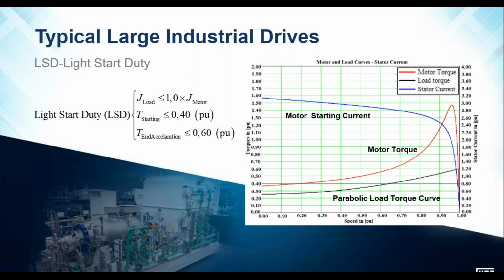So just as a reminder, we defined a light start duty as the load inertia being less than or equal to the rotor inertia of the motor, a starting torque requirement of 0.4 per unit of the motor's nominal value, and an end of acceleration torque less than or equal to 60% of the nominal rating of the motor.